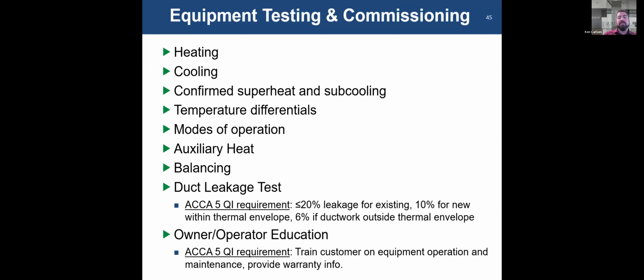The guidelines basically are for existing systems. If you were to actually do a duct leakage test, you should be less than or equal, no more than 20% leakage rate. For new systems within a thermal envelope, no more than 10%. And if your ductwork is outside the thermal envelope, basically if you're in a crawl space or an attic, it's no more than 6%. So back to the conversation we had earlier about sealing up ductwork. If you don't seal up all your connections, you'll never meet these requirements. All right, your ductwork can be very, very leaky if all connections are not sealed. So take the little bit of extra time to seal all your ductwork connections before insulating, and you won't have a problem with duct leakage.